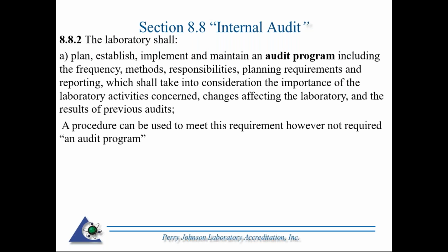All right, 8.8.2a, the laboratory shall, as you know, is a requirement. So whenever you see that word shall, that is a requirement. Laboratories shall plan, establish, implement, and maintain an audit program, including the frequency, methods, responsibilities, planning requirements, and reporting, which shall take into consideration the importance of the laboratory activities concerned, changes affecting the laboratory, and the results of previous audits.